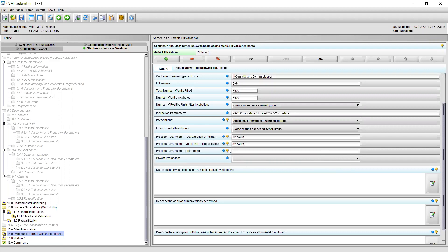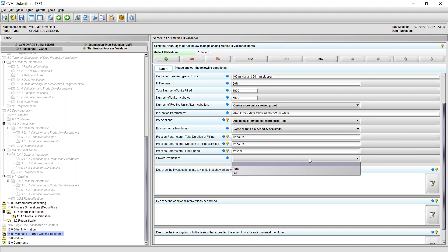In field 13, provide the line speed during the media fill, for example 12 vials per minute. Note that the line speed may be represented by whichever unit of measure you choose, and may be reported as a range from minimum to maximum or as an average line speed for the media fill. Lastly, in field 14, state the results of growth promotion testing by selecting a response from the drop-down menu — select either pass or fail.